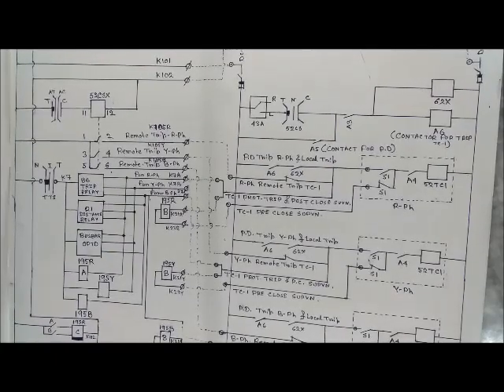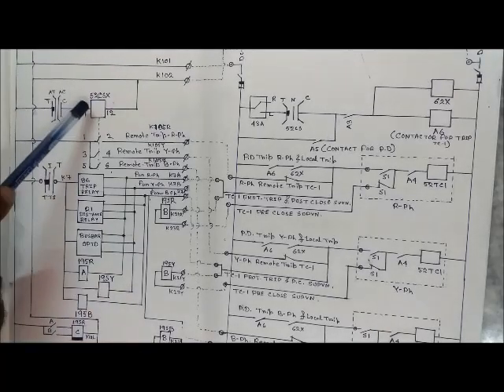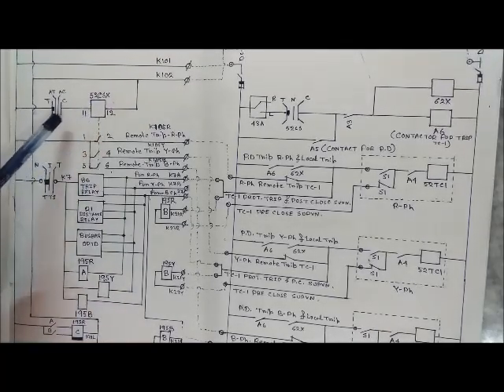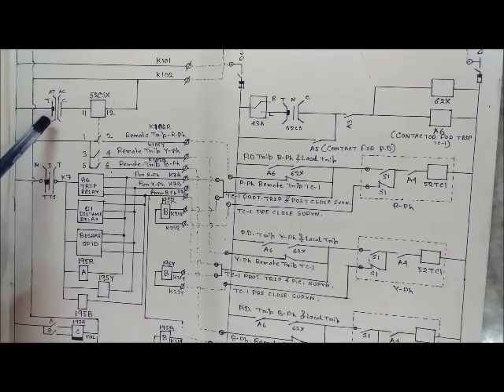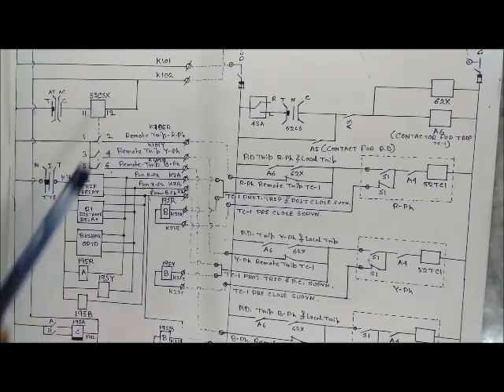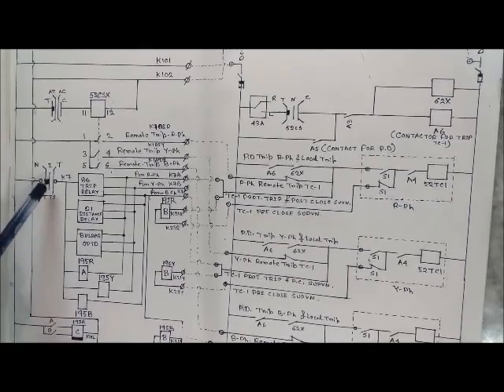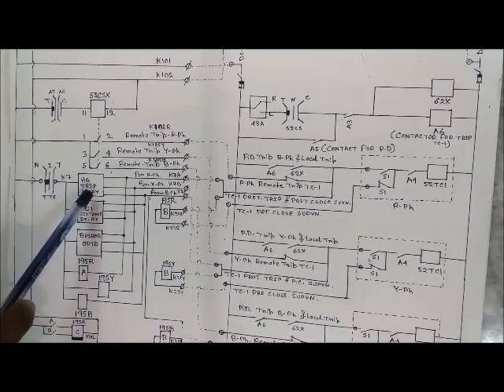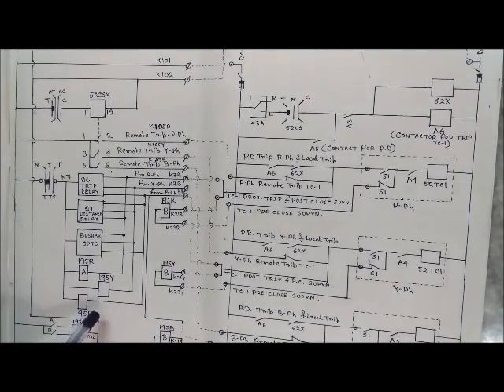K101 and K102 are the TC1 positive and TC1 negative. 52CX is the contact multiplier for the tripping pulse from the control switch located at the control and relay panel. NIT is the normal-inter-transfer contact of the trip transfer switch — this switch should be in normal or inter position for tripping its own breaker. Contact 86 is the trip relay contact, 21 is the distance relay contact, and there is a contact for bus bar protection. 195R, 195Y, and 195B are the trip circuit supervision relays for R phase, Y phase, and B phase respectively.